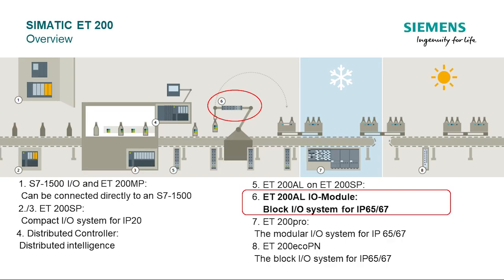Looking at the plan overview, you can see that Siemens offers a variety of different I/O formats. The type you choose is based on your I/O and mounting requirements — whether it's mounted in a central cabinet or on the machine. In the case of the ET200AL, it is lightweight and designed for distributed architecture. It is IP65-67 rated, along with a 10G vibration rating and wide temperature range, making it suitable for machine mounting and on-arm mounting for a robot.